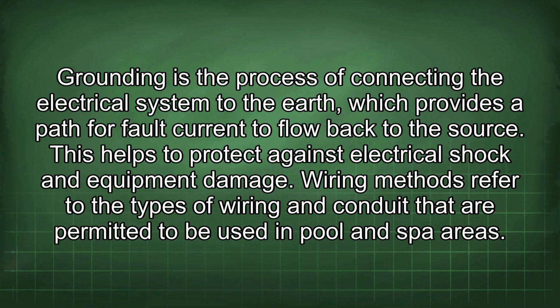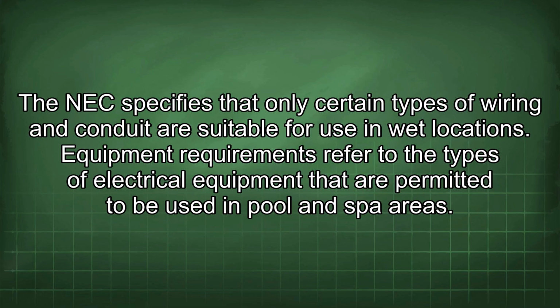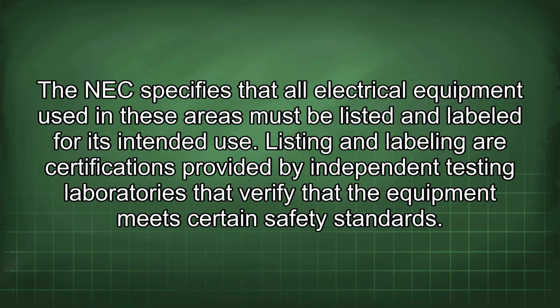Wiring methods refer to the types of wiring and conduit that are permitted to be used in pool and spa areas. The NEC specifies that only certain types of wiring and conduit are suitable for use in wet locations. Equipment requirements refer to the types of electrical equipment that are permitted to be used in pool and spa areas. The NEC specifies that all electrical equipment used in these areas must be listed and labeled for its intended use. Listing and labeling are certifications provided by independent testing laboratories that verify that the equipment meets certain safety standards.